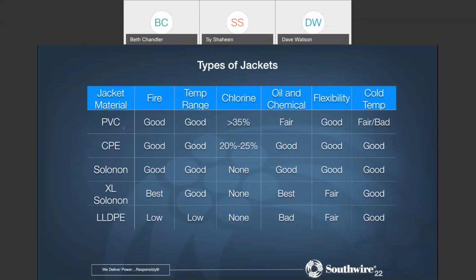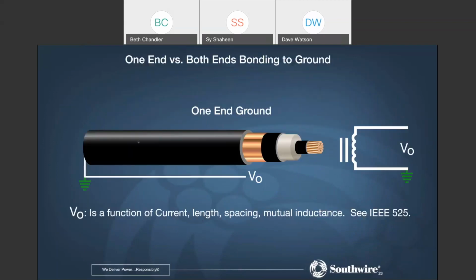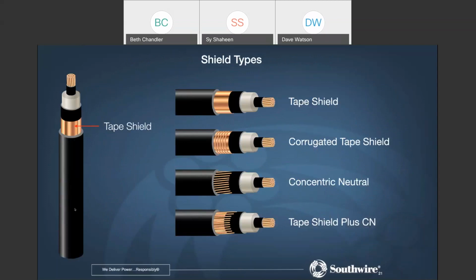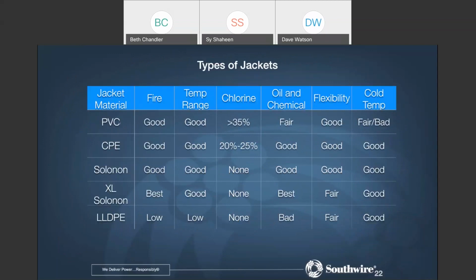There are different jackets. We see most of the jackets in the data center world, and we're talking about this part of the cable construction. Mostly it's PVC, polyvinyl chloride. It's one of the more economical. It's pretty good, but it's loaded with chlorine, hence the word chloride in polyvinyl chloride. If the cable catches on fire, it releases chlorine gas, and when chlorine gas mixes with any humidity or water, it turns into hydrochloric acid, which when it lands on any equipment, will corrode it. Some companies go with CPE, chlorinated polyethylene. It still has chlorine, but not as much as the PVC.